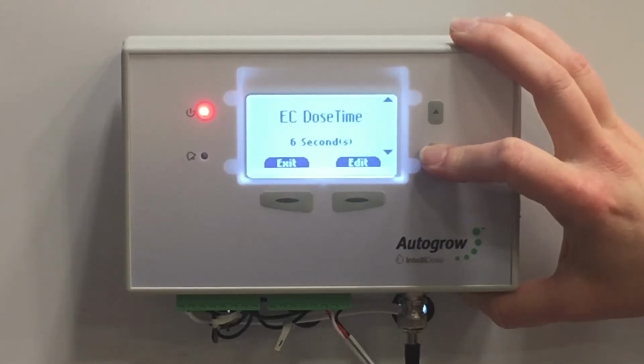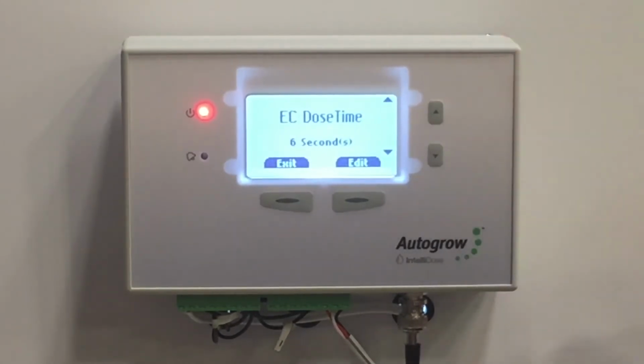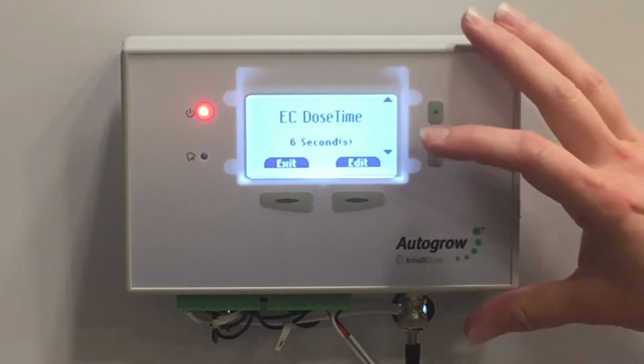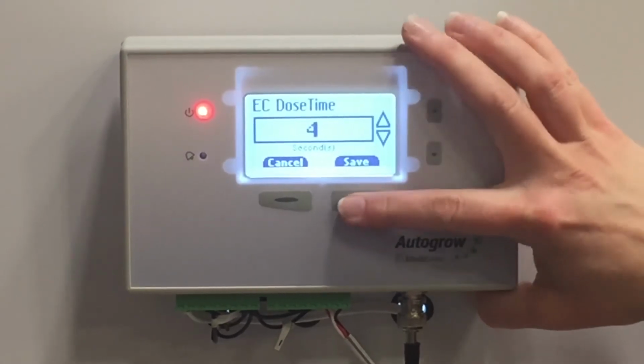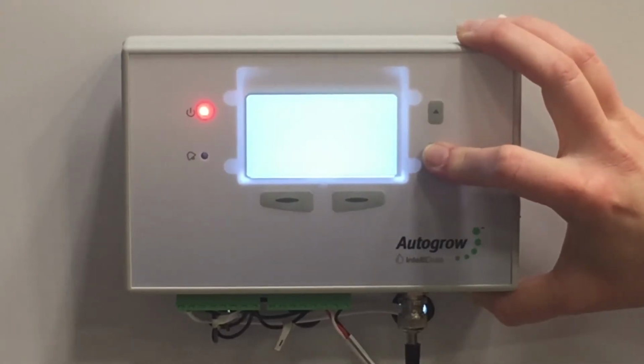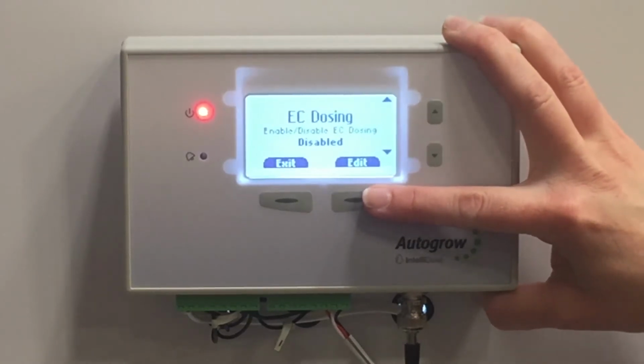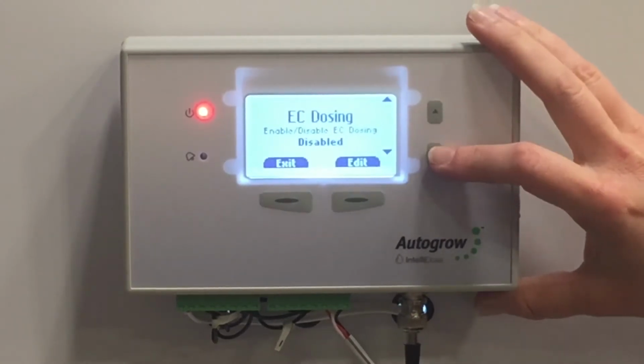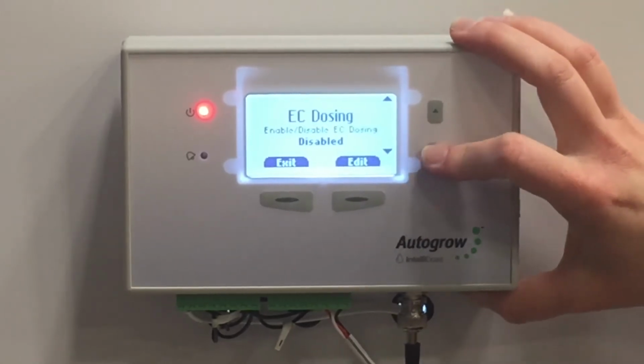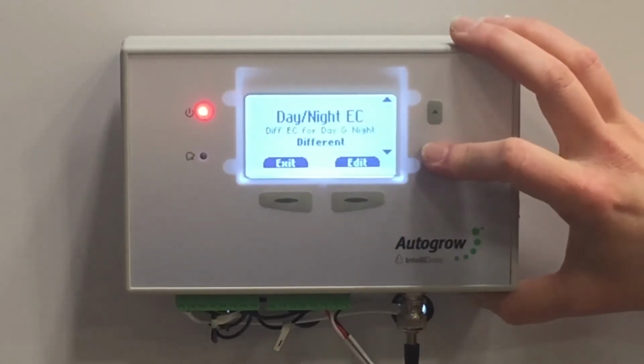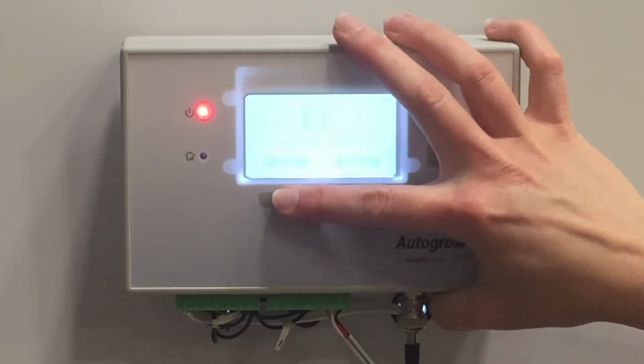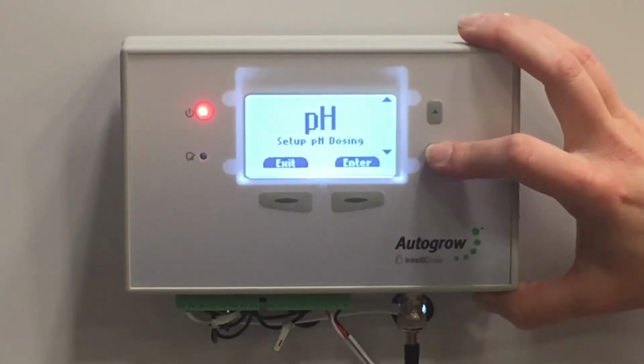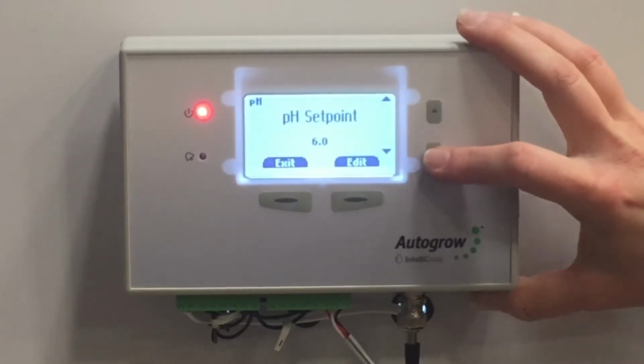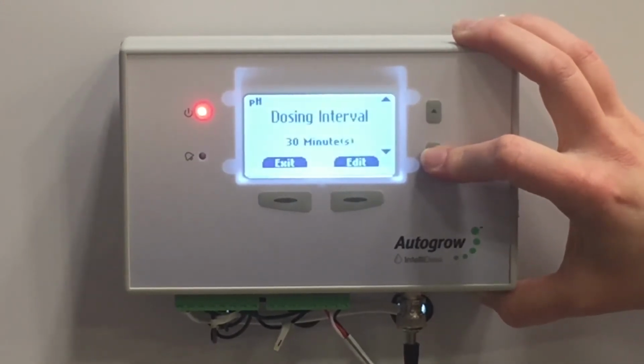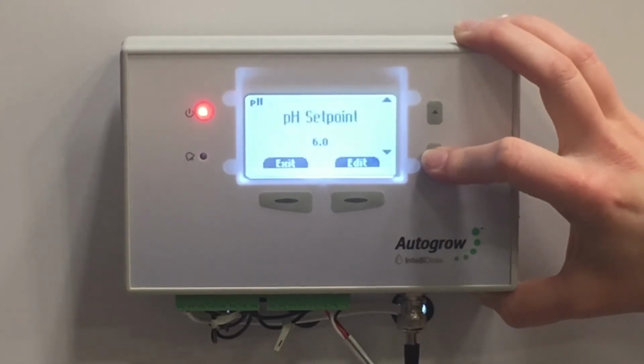Then you have your dose times and your dose intervals. The dose time is how long the peristaltic pump stays on per dose. The dose interval is how long it waits between doses. To change this, simply hit enter, change, and hit save. You can also enable and disable the EC dosing here. So while you're cleaning out your tanks or if the system goes into disuse, you can just disable it. And if you have a different EC for day and night. To exit out of the EC settings and go into pH, simply hit exit, go into pH dosing, and once again you can set your set points, your dose times, your intervals, and enabling or disabling it.